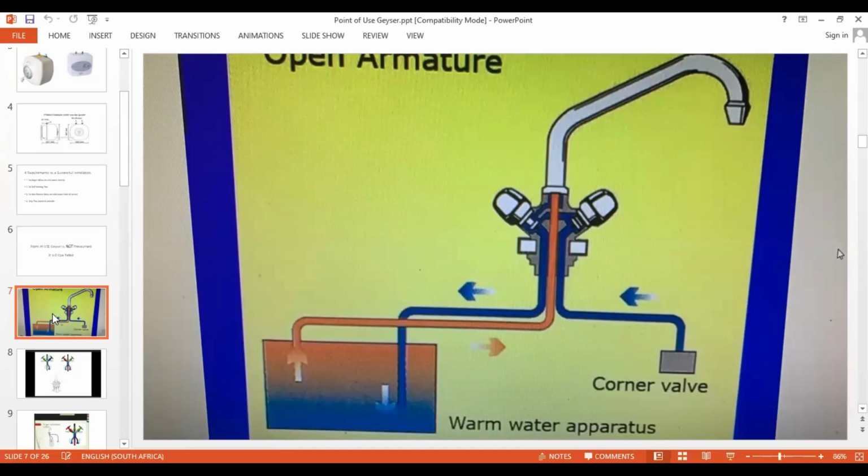So now you're already halfway there. The remaining pipe will be the one that you can blow through, and that you connect to the hot water outlet of the vessel. And then you install a drip tray, which must be piped to the outside of the building. You cannot connect the drip tray outlet pipe to the waste pipe of the sink. It must, like in the normal SANS 10254 drip tray requirement, be piped to the outside where it can discharge in a visible place where it will not cause damage to property or be a nuisance.